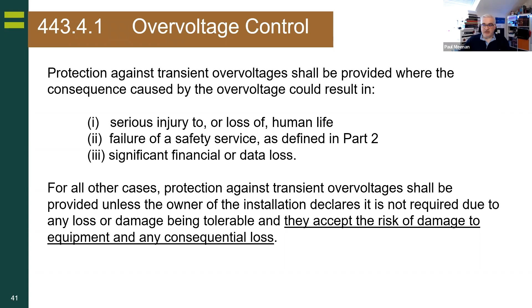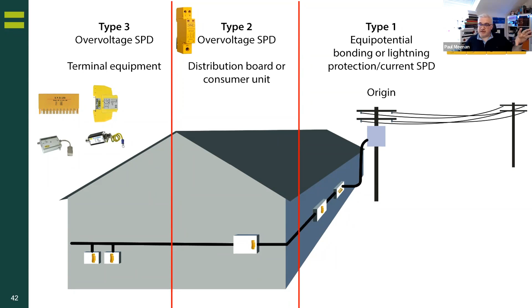But for those who may not be familiar with surge, nice picture to break it up. Type 1 you generally put on your mains from transient over voltages that enter the building. Type 2 would be at your local boards and consumer units. Type 3 at your more sensitive equipment. In a nutshell, for me, my railway, type 1 is on my mains, every fuse board with a type 2, and then type 3 will be at my ticket machines to protect those vulnerable circuits because I've got 25,000 volts within a few meters. So it's sensible.